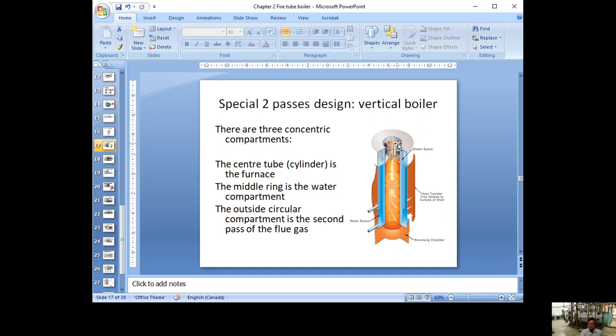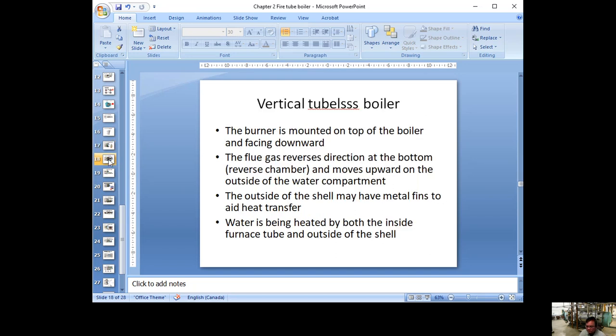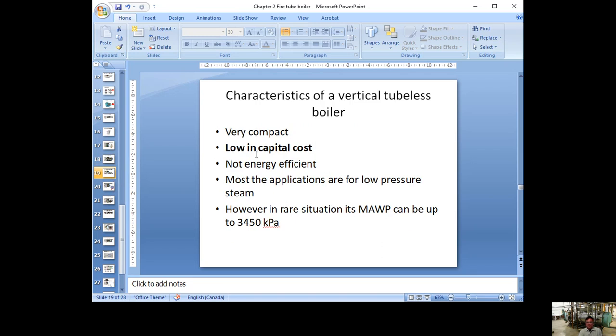The fire will be touching the water compartment from both inside and outside, but because the compartment is quite thick, the heat transfer is not very efficient. I showed you one of the Fulton boilers — only about one meter diameter, two meters high, and it can produce steam already. Because of its simple construction with only three compartments, the initial capital cost is really low.